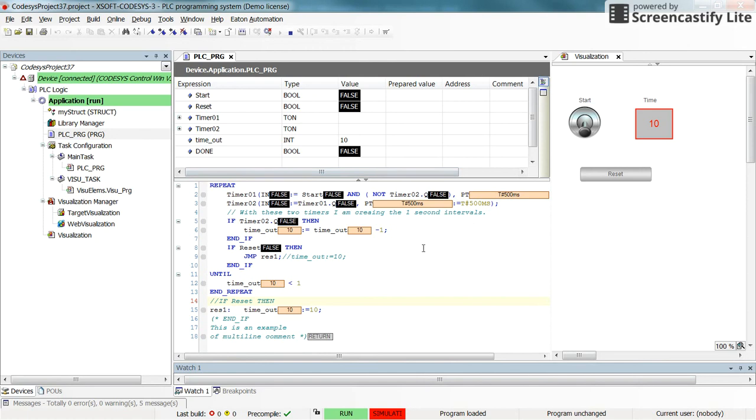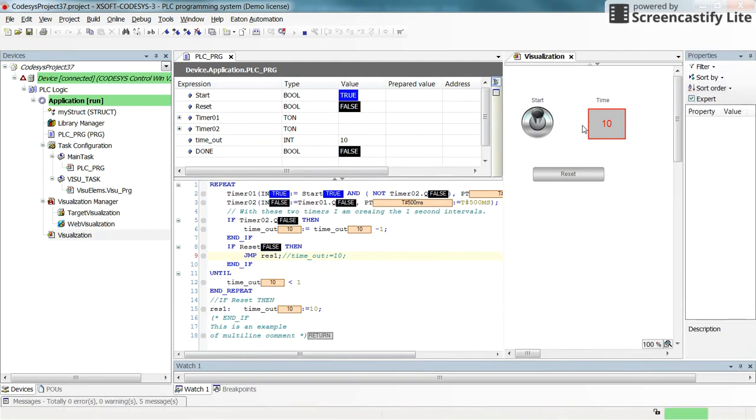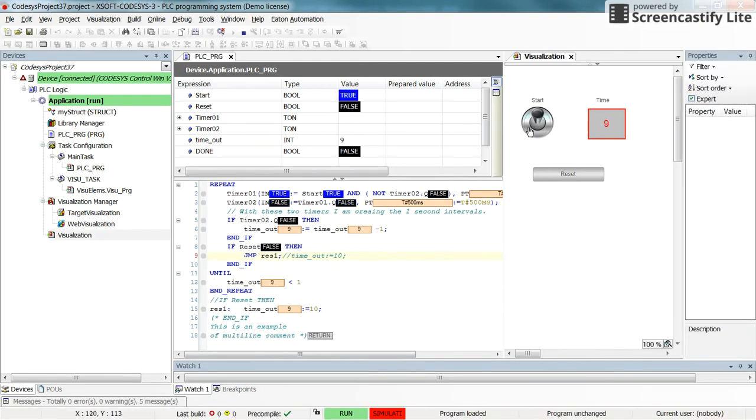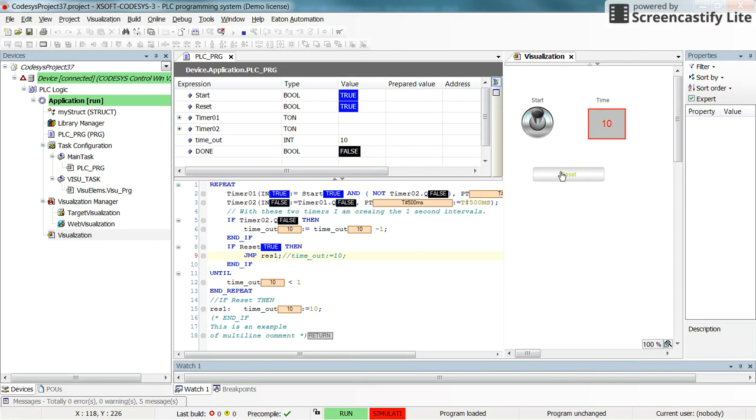Let's check how the jump works here. If I set the start to true, we'll have the timeout going down. If I press the reset now, you see the value for timeout becomes 10. Whenever I press and hold the reset, the execution jumps here. In the if reset then jump to reset, it jumps to line number 15 and the value for timeout becomes 10.